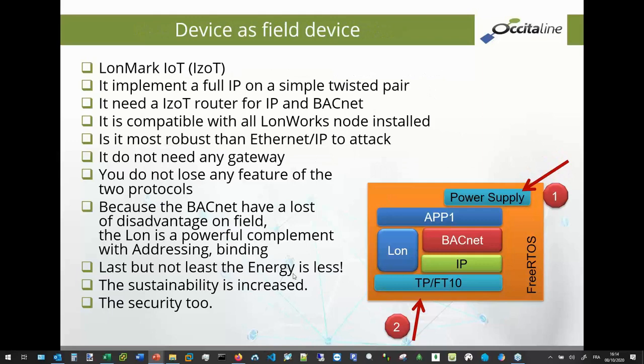And because of this operating system, Linux or FreeRTOS, you can have some attacks, because the hackers are very intelligent in general, and they try to check on the CVE database if a device is not up to date with its operating system and so on, and the attack arrives very easily. In fact, Ethernet and IP are more sensitive than field devices based on a simple protocol like Modbus, KNX, LON on TP/FT, or BACnet MS/TP.